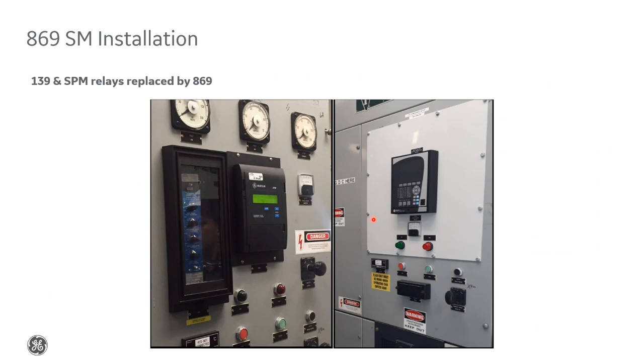Quick installation example. This is from one of our first 869 SPM installations done, I think at Dow Chemical in Texas, if I'm not mistaken. They originally had an old 139 relay that did stator protection and an SPM relay beside it for control. They were able to retrofit this entire panel with a new 869 with the SPM option, same panel, and now they can do everything in one device instead of two.